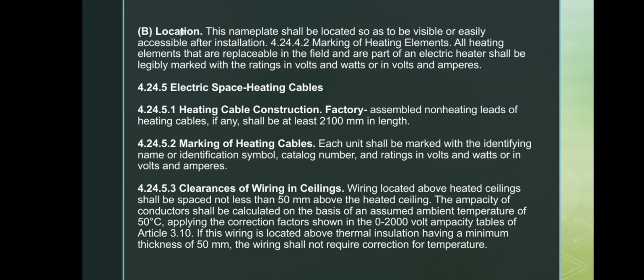For heating cables, any non-heating leads must be at least 2100 mm long, and each cable must be marked with the manufacturer's name or symbol, model number, and its electrical rating. Wiring above heated ceilings must be 50 mm or more above the heating area, and conductor ampacity must be based on an assumed temperature of 50 degrees Celsius. If the wiring is placed above at least 50 mm of insulation, no temperature correction is needed.